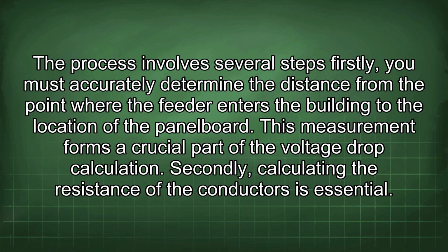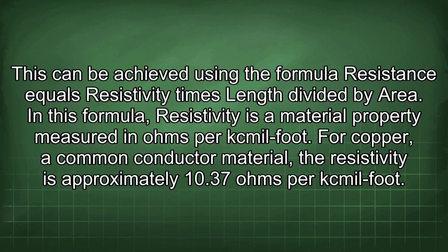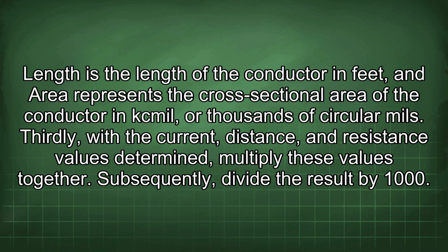Secondly, calculating the resistance of the conductors is essential. This can be achieved using the formula resistance equals resistivity times length divided by area. In this formula, resistivity is a material property measured in ohms per kcmil foot. For copper, a common conductor material, the resistivity is approximately 10.37 ohms per kcmil foot. Length is the length of the conductor in feet, and area represents the cross-sectional area of the conductor in kcmil, or thousands of circular mils.